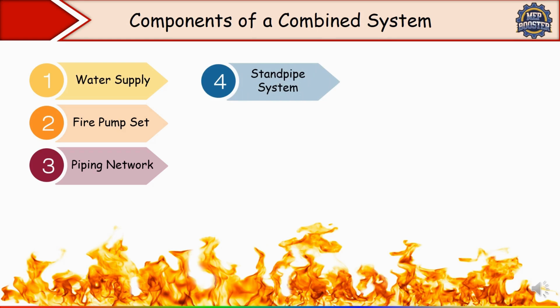Okay. Then the next component is standpipe system. So here we have a hose connection, typically 2.5 inch outlet with 1.5 inch reducer for fire department use. Okay. So we have 3 types of standpipe system. Okay. As I discussed earlier, class first, second or third, based on user type and hose size. Okay, in class first standpipe system, normally we have a 2.5 inch hose connection. And if you go for class second, so here we have a complete hose station, 1 or 1.5 inch hose station. And class third is the combined of class first and class second.